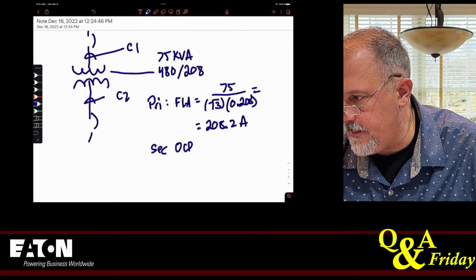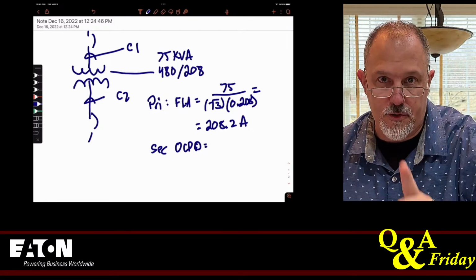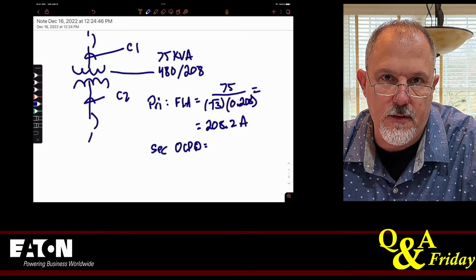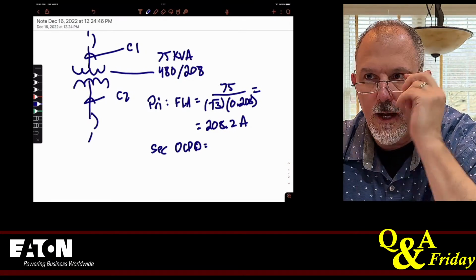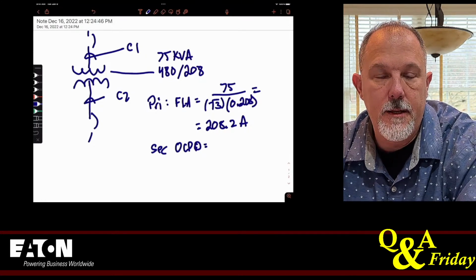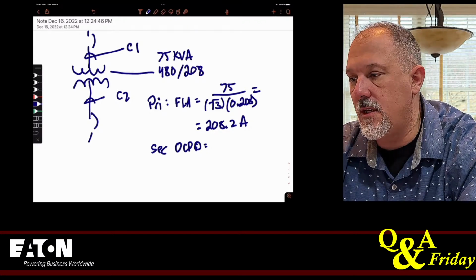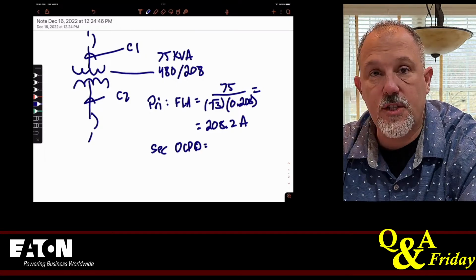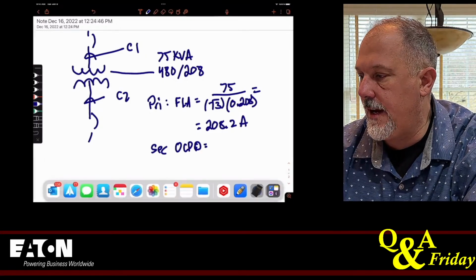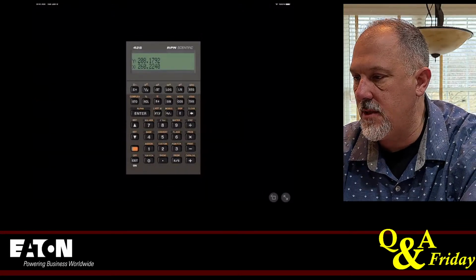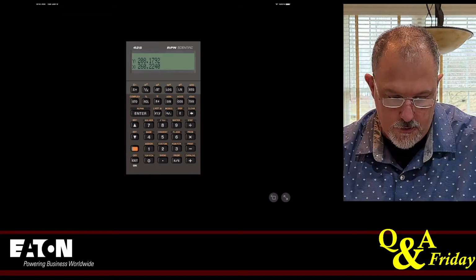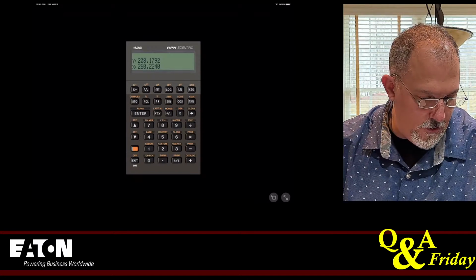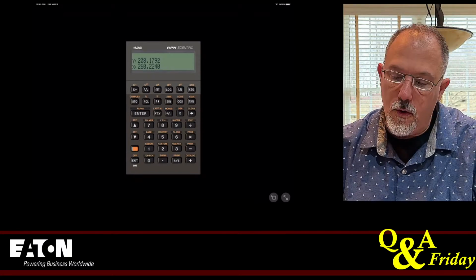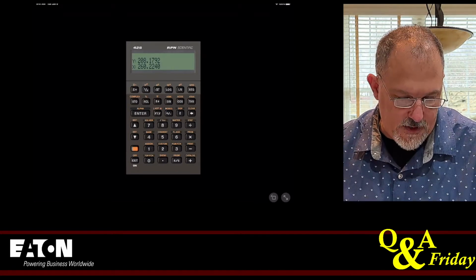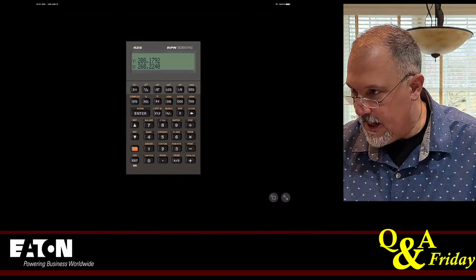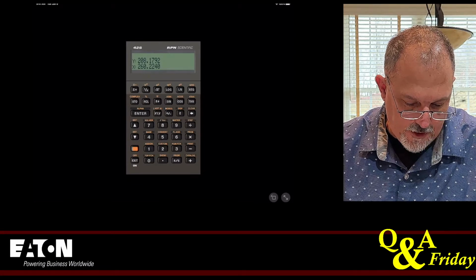For the secondary OCPD, I always say pick the OCPD first, right? Because how are we going to pick an overcurrent protective device? If it's going to be the main in a panel board, I have to know what panel boards I can pick that I can put a main in. So my maximum size is 1.25 times 208, and I can go to the next higher. Multiplying by 1.25 gives 260. Article 240 has a nice little table of the standard ampere ratings, 240.6. I'm at 260, so that means I can go to 300 amps.